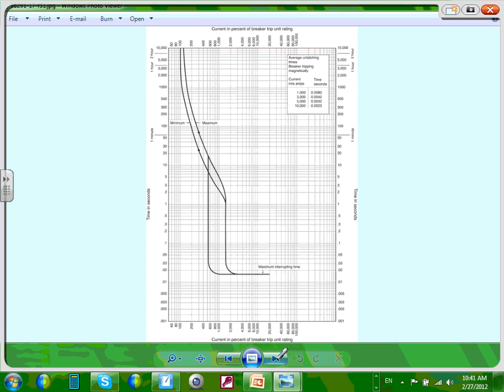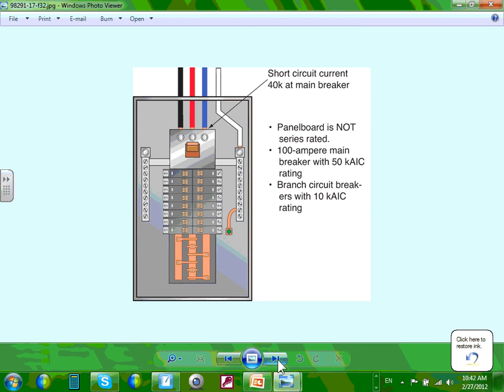Circuit breakers have two values for them. They look like this. One of them is the max and one is the min. Because circuit breakers are mechanical equipment, it takes them time to sense and open, versus the fuse, which burns. With the curve, we can predict that it's going to sense and open between the minimum and the maximum. So for them, they give you the minimum. Between this value, we know it's going to start the opening process. At the max, it will completely open. Again, this will be for next quarter when we get into that.